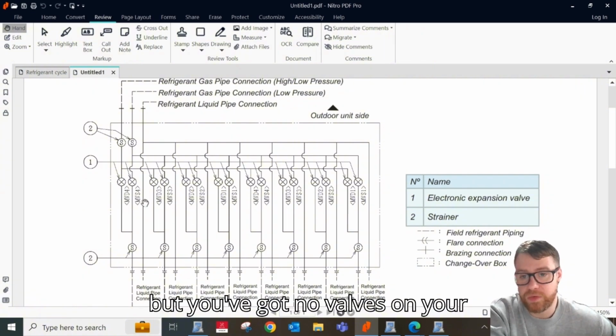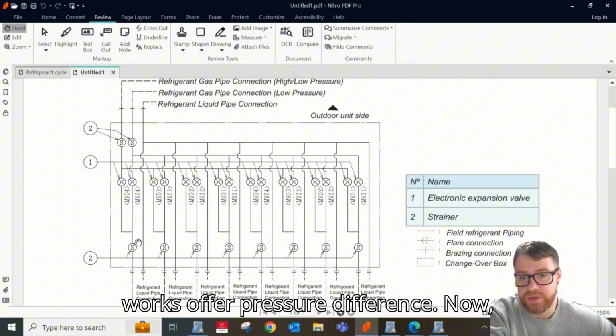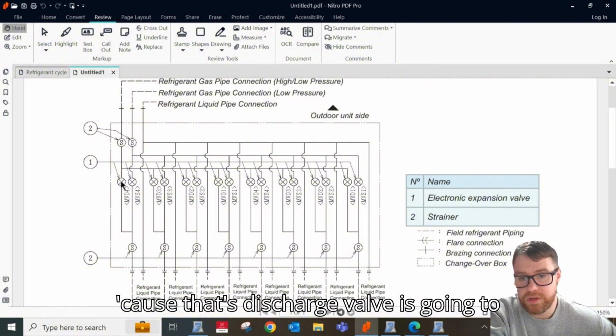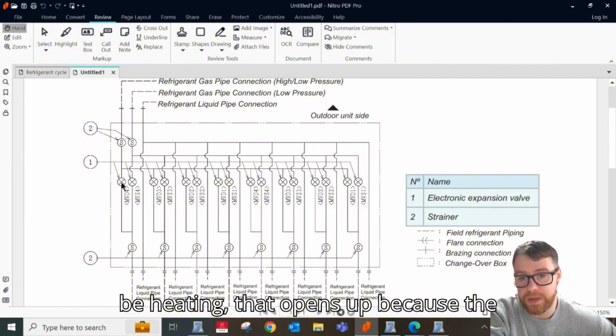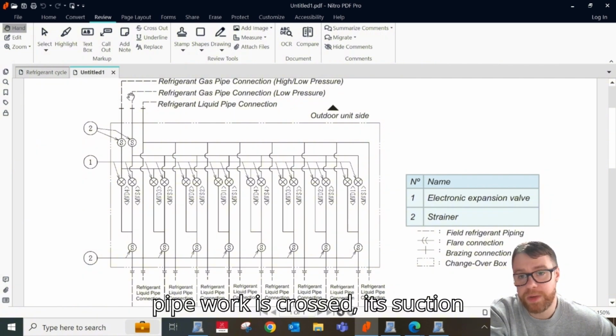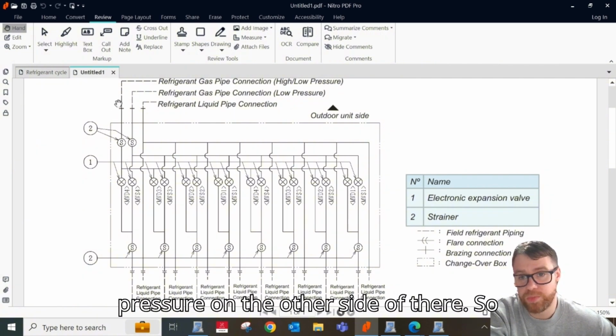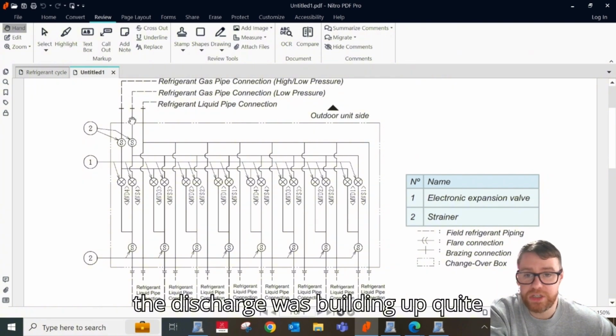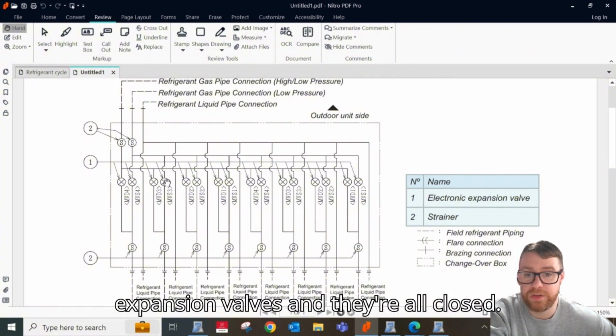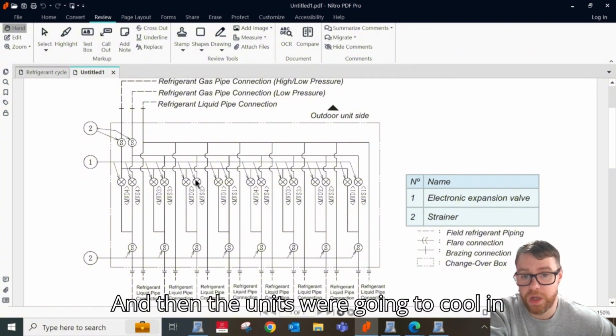But you've got no valve other than on your liquid pipe other than your indoor, so it always works off a pressure difference. Now, because that discharge valve is going to be open to heating, that opens it up, but because the pipework is crossed, it's suction pressure on the other side of there. So the discharge was building up quite quickly because it's hitting these expansion valves and they're all closed.